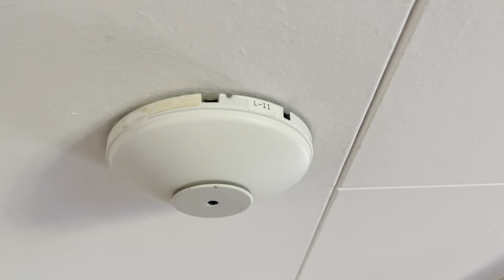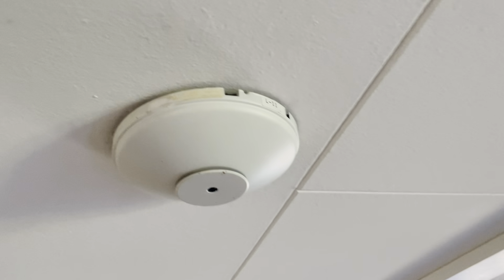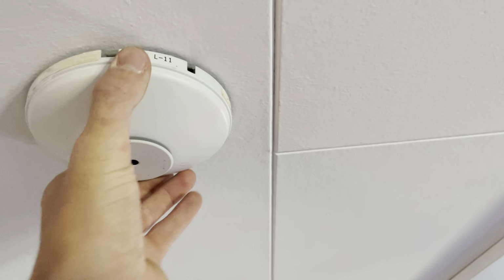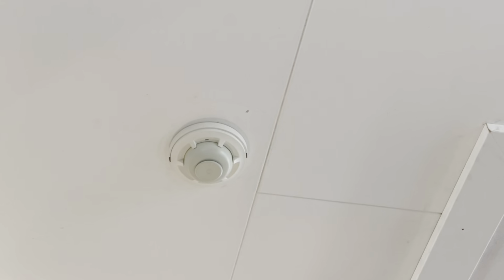We just popped another Edwards 281 series, I believe. Not doing too good. That's three for this school today, and I remember last year it was like three. These are definitely recalled for a legitimate reason, that they don't activate. Yeah, there it goes. New detector is installed, now we're just gonna test it.